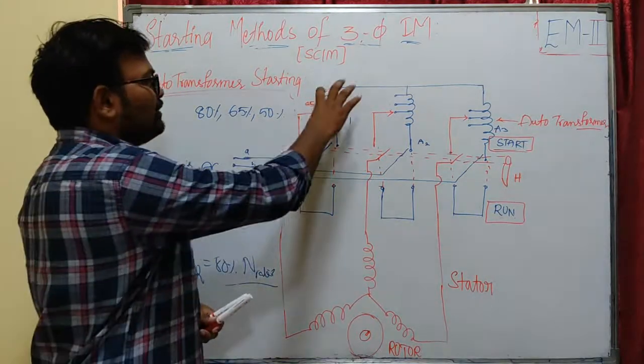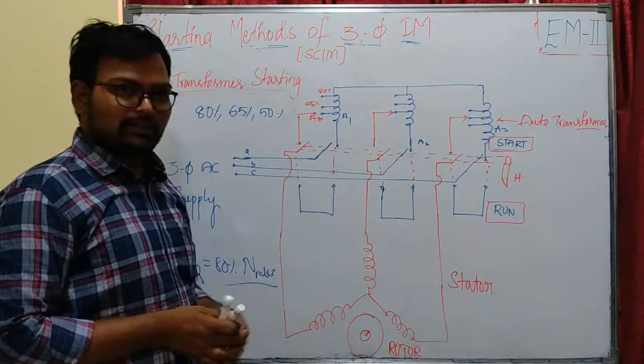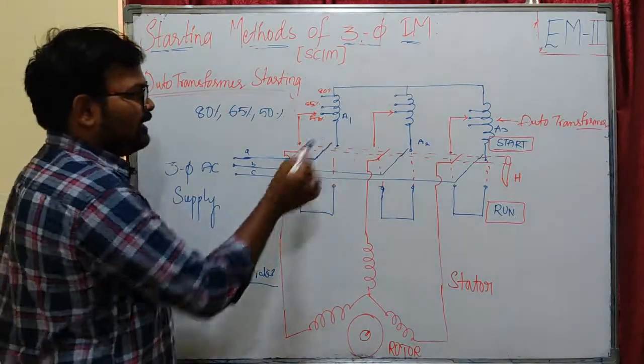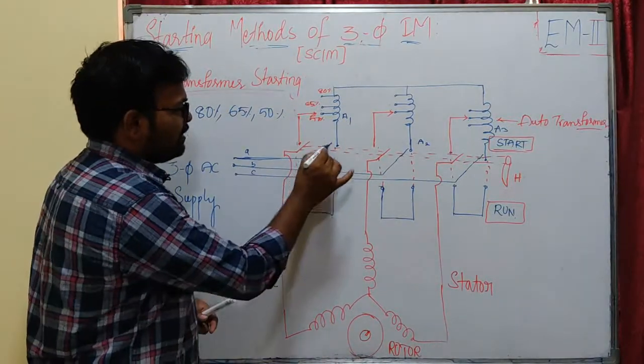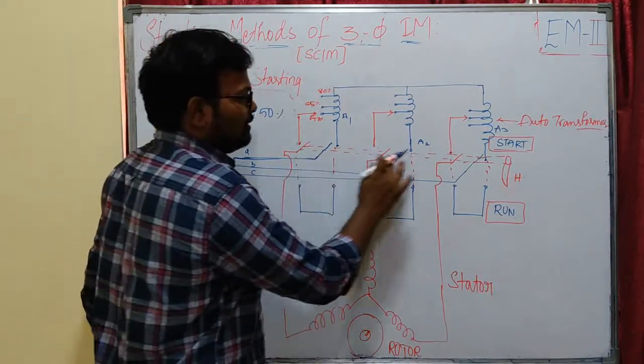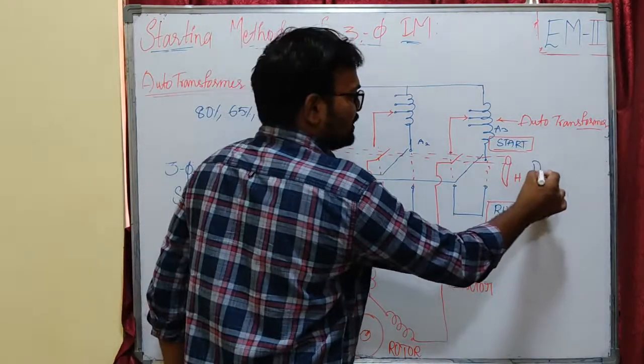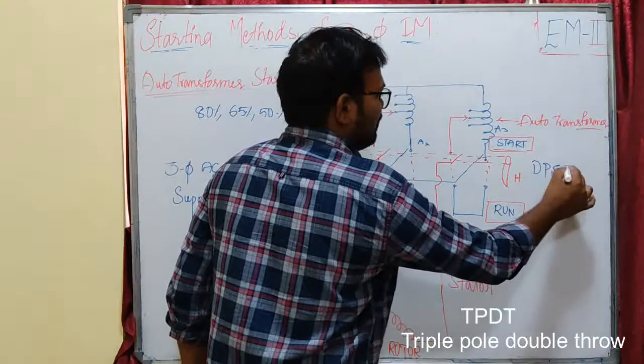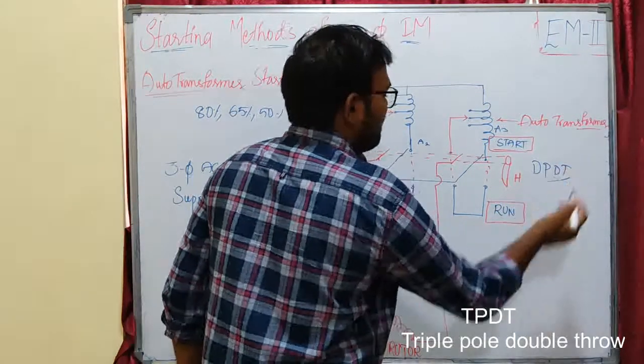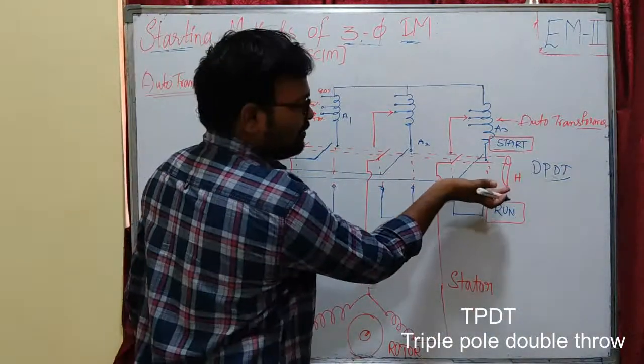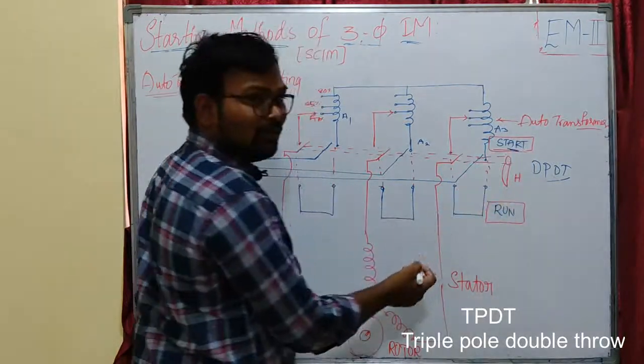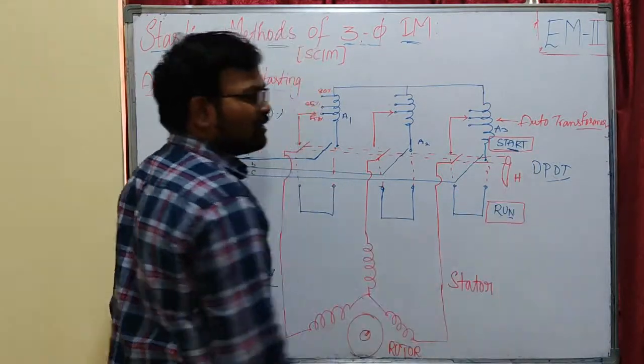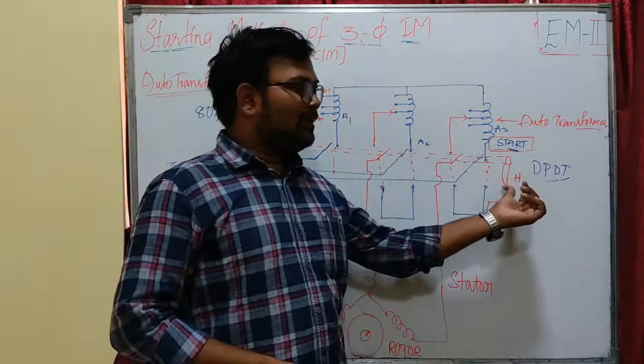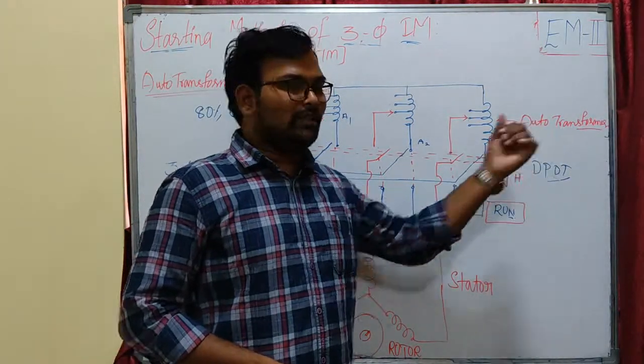So these three are the reduced voltages that are going to be applied to our stator circuit. You can see here the A1 auto transformer 1, my supply line is coming like this, and when I switch this DPST switch, this is our DPST switch, double pole double throw, DPDT, it can be turned on to the starting position, this is the start position, and it can be turned on to the run position. At the time of starting, this switch is in the start position.